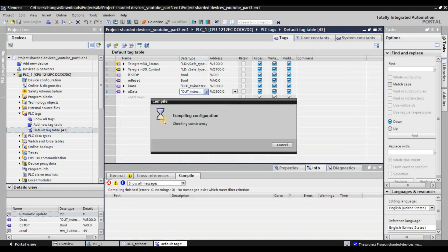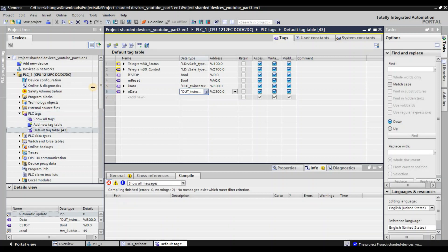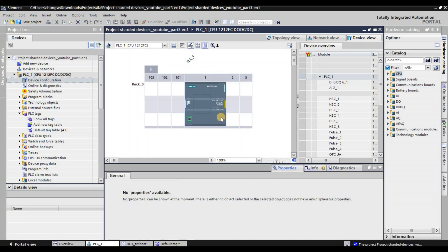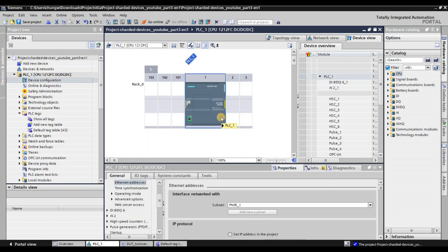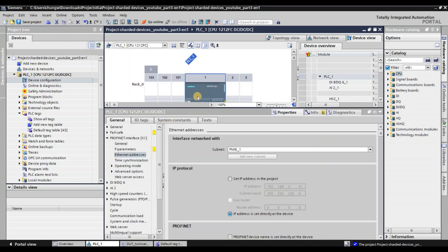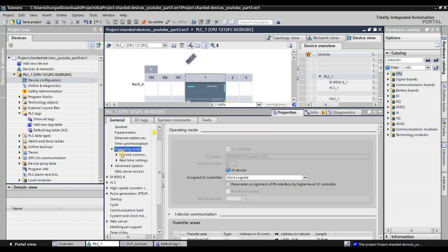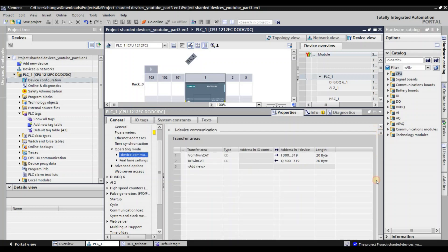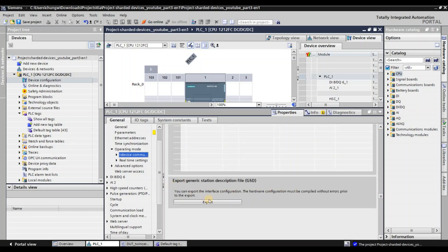Now we can save the project and compile it. Finally, we can export the GSDML file of our S7 1200. As mentioned in part 4 of the videos, if you need to configure a Profinet network, each GSDML file is necessary and needs to be imported to your Profinet controller. Click the S7 1200, go to operation mode, and iDevice combinations. There is an option called 'Export Generic Station Description File GSD.' Let's export it. Done.